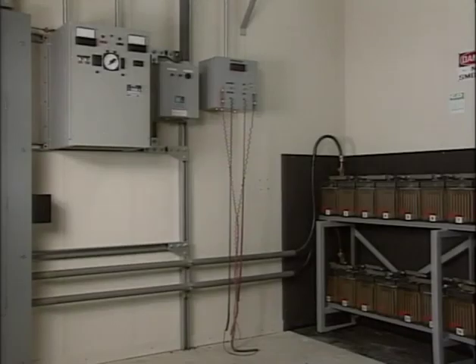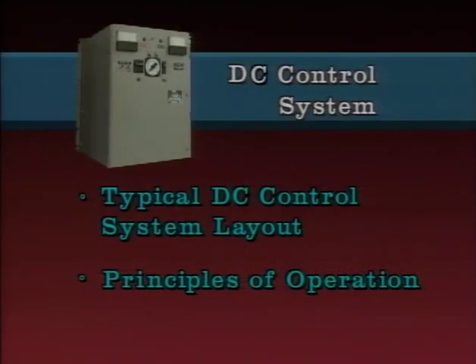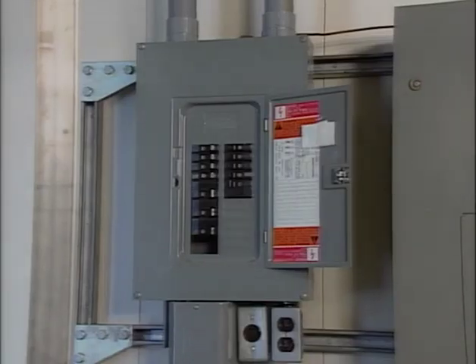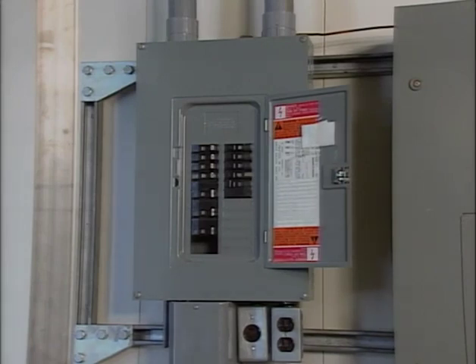In order to clearly understand the role of a charger in a DC control system, it's necessary to know what a typical DC control system layout looks like and how the system works. This part of the program will describe a typical DC control system, covering the layout and the principles of how the control system works. The first part of a DC control system is located at the AC supply panel, which is the source of alternating current to the battery charger. A breaker in the AC supply panel controls the supply of AC power to the charger.